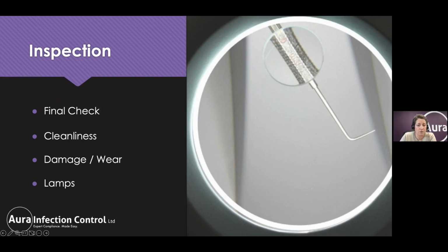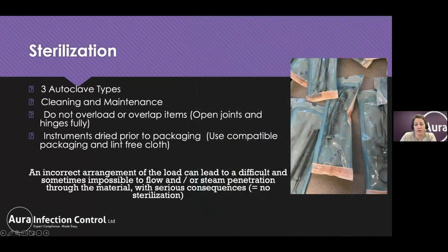And once we inspect and sign them off, that means we can put them through to our final stage of sterilization. And this is what we're going to use to render a surface free from viable microorganisms, including spores. It would not necessarily deal with things like prions. They would not be effectively destroyed by this process. Now, in our country, we have three different types of autoclave in use in practice. So we have type B, or vacuum autoclaves, N, or non-vacuum autoclaves, and S types. They are all designed for a different load type.